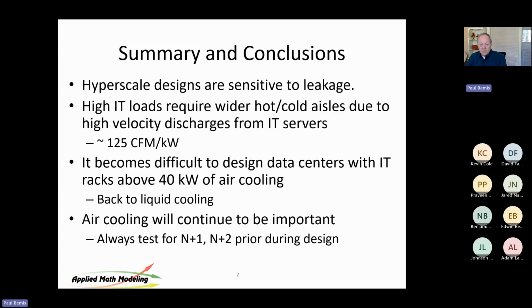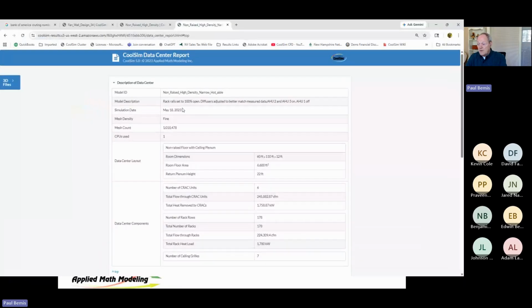So let me just bring up an output report again and show you that up at the top. I ran this one on fine because I wanted to get the mesh count up high enough to be able to see all the path lines. Path lines are correlated to the mesh. So the denser the mesh, the more you'll have. And if you're not seeing any, turn up your density. By the way, if your density is not in a million cells, you need to get it there because you really want it up in this range, at least for most models. There are some simple models that don't require that because the rooms are small. But you want your density to be up there. I like to see it near a million.